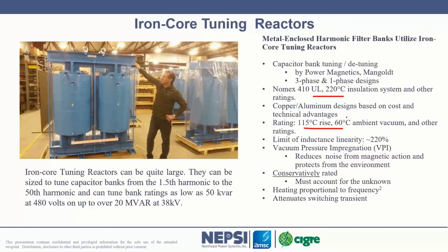The key here, though, is what ambient temperature you pick. Make sure you pick the correct ambient temperature. For us, we always pick at least 60 C ambient inside the enclosure. Even if it's a 40 C ambient, we'll pick a 60 C ambient temperature inside the enclosure. Why? Because inside the enclosure is hotter than outside the enclosure. So it's important that you properly specify the ambient temperature, because the reactor design will be impacted by that ambient temperature.